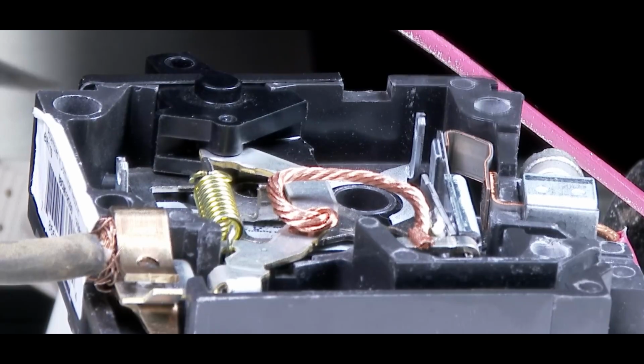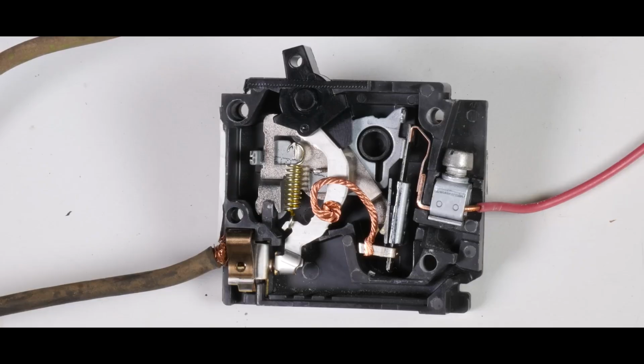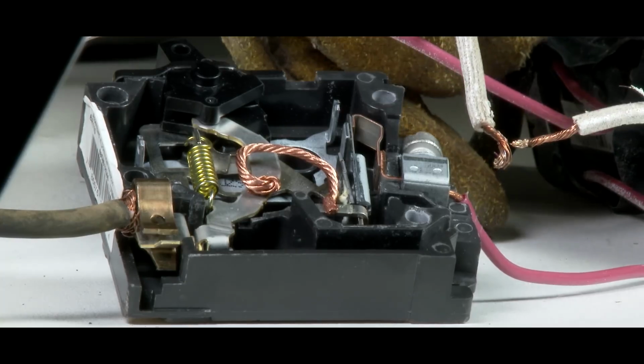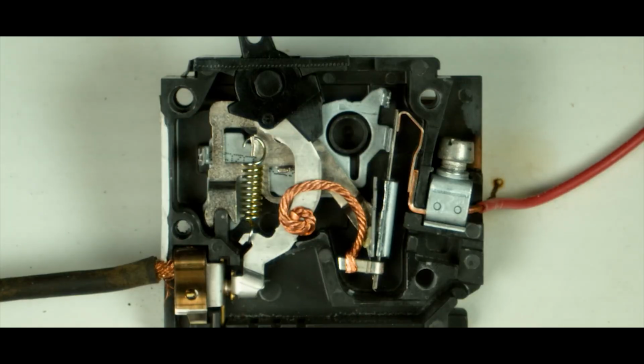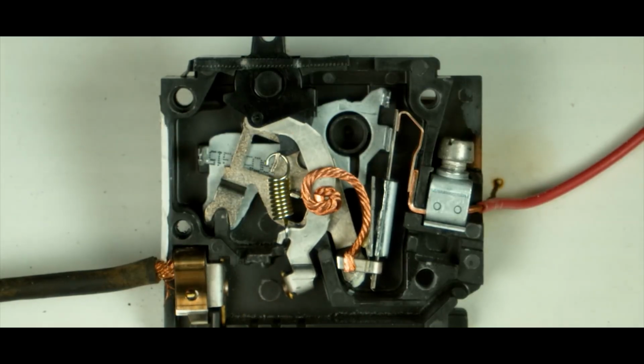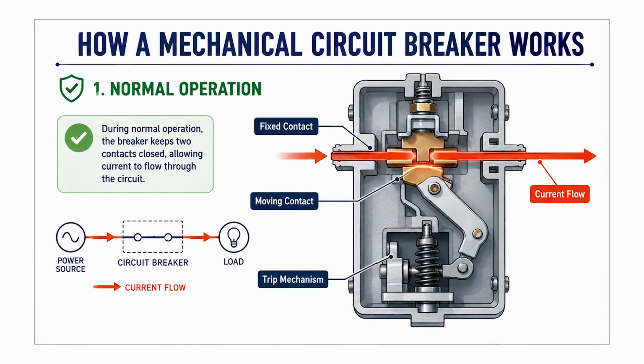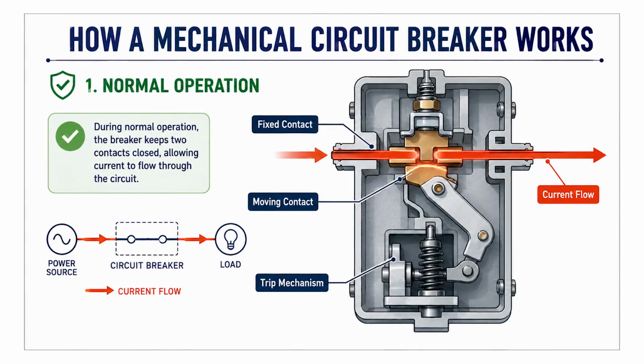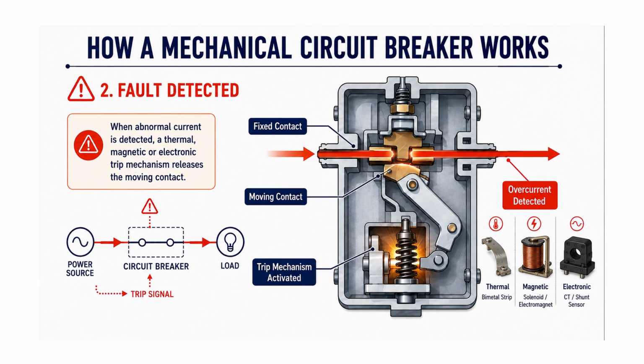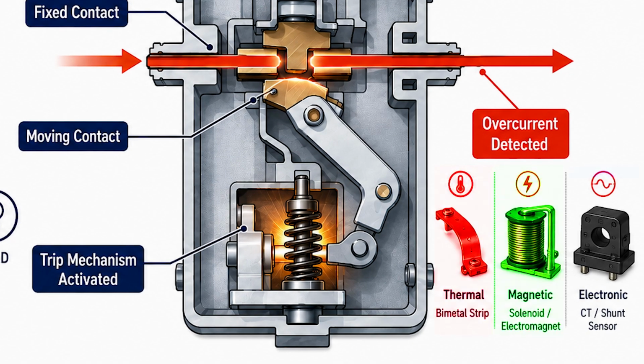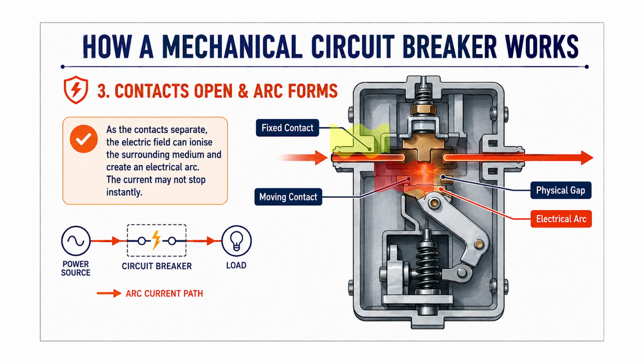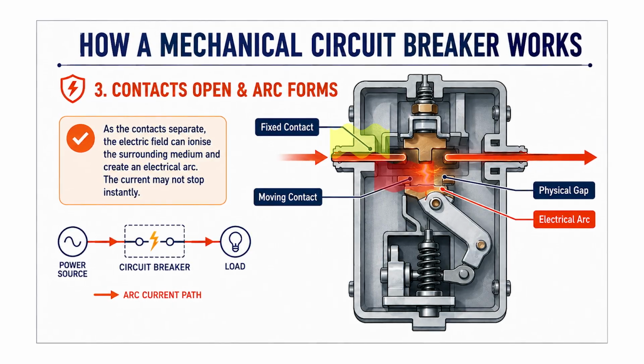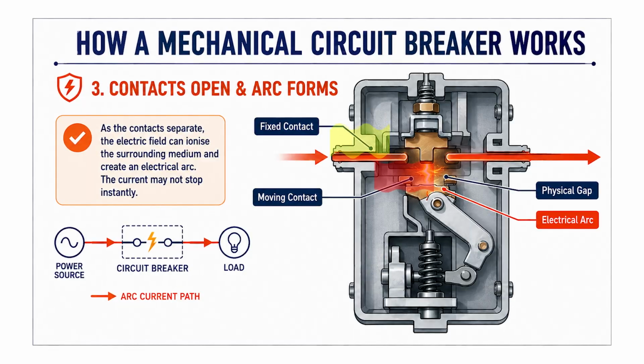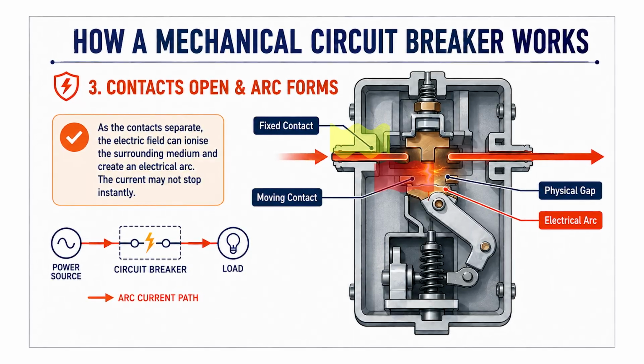Before diving into the solid state circuit breaker, let's look at the traditional mechanical circuit breakers, which are being used traditionally, how they work at a surface level, and their contrast with the solid state circuit breaker, so that we can understand the architecture. During normal operation, a mechanical circuit breaker keeps two electrical contacts closed, allowing current to flow through them. When an abnormal current is detected thermally, magnetically, or electronically, a control trip mechanism releases these moving contacts. As these contacts begin separating, a physical gap is created in the current path. But the current doesn't stop as the contacts start separating from each other.